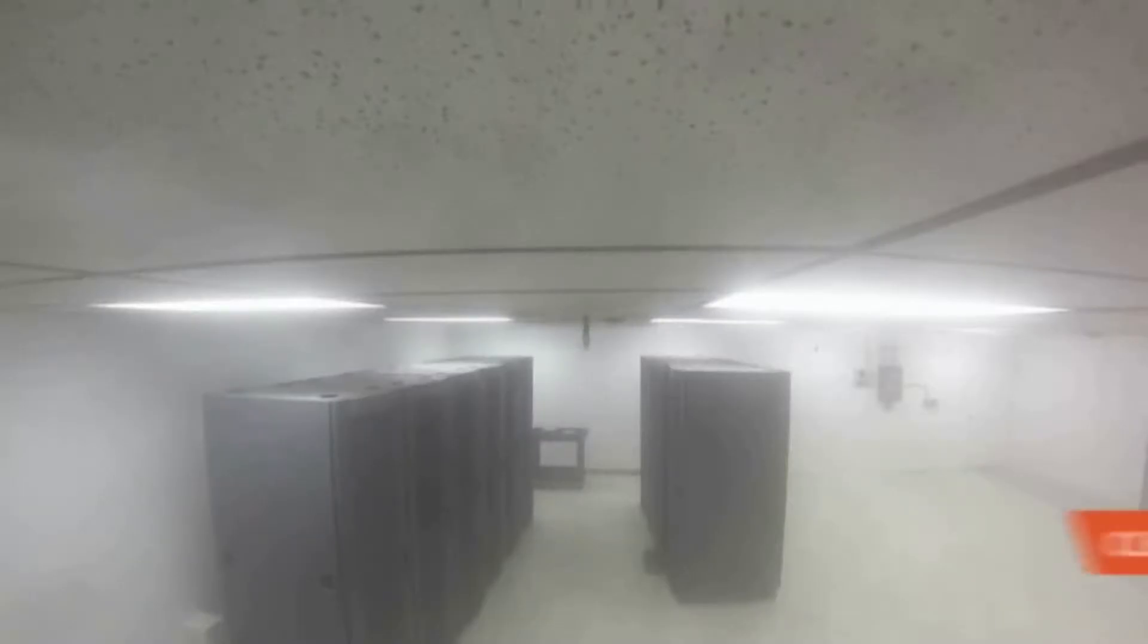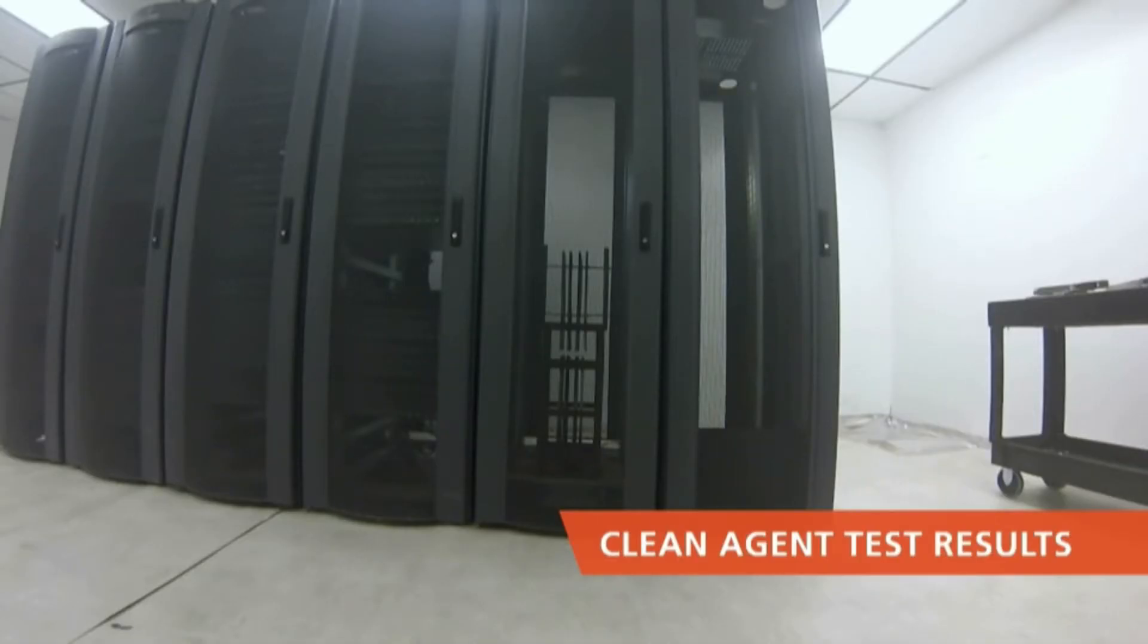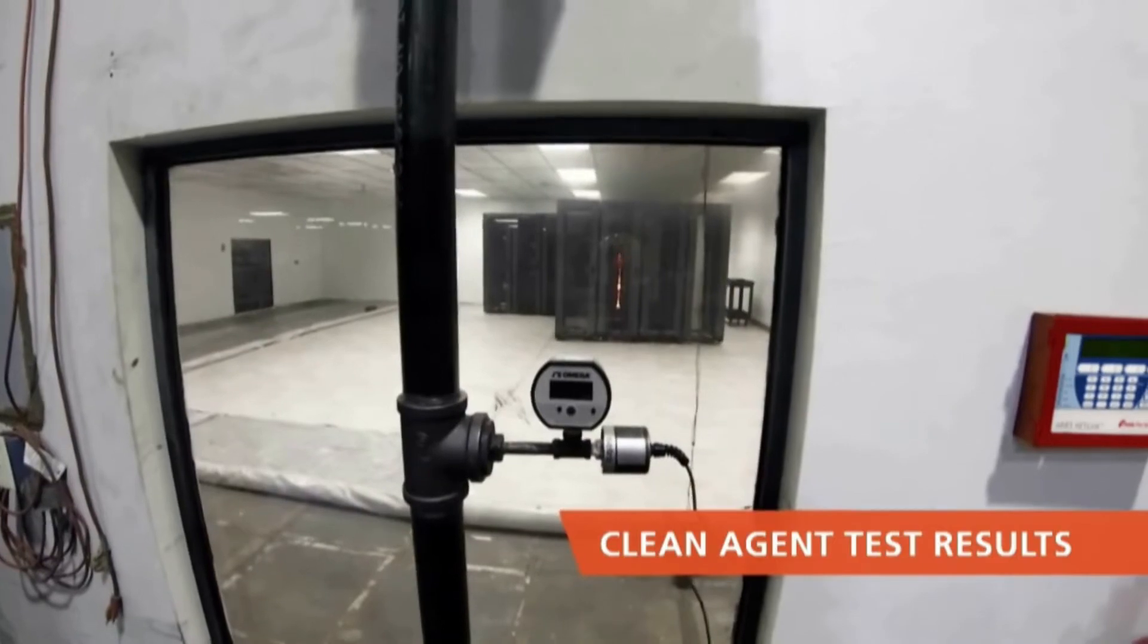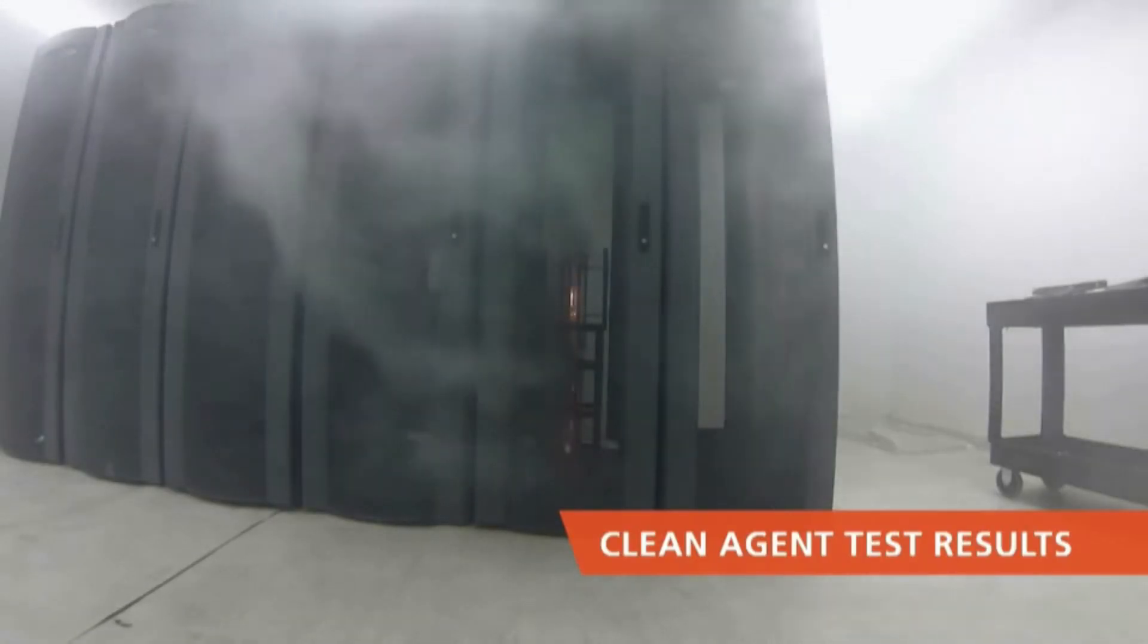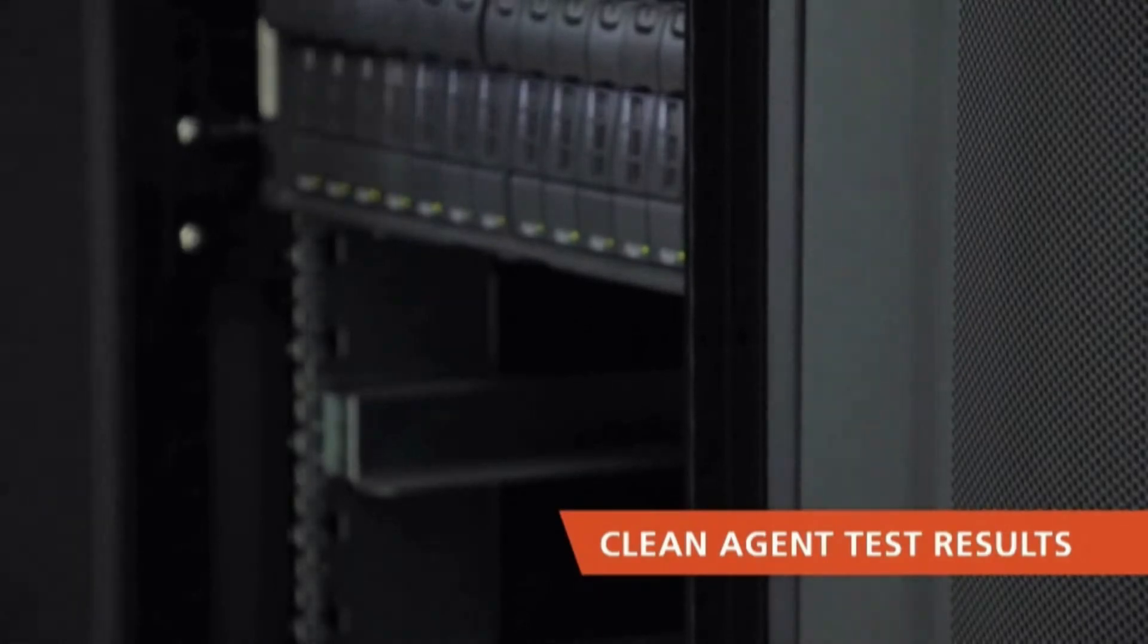The results of the Kidde clean agent system test are dramatically different. Even though the cabinet temperature reached 230 degrees Fahrenheit before the agent discharged, the room and servers show virtually no sign of damage.